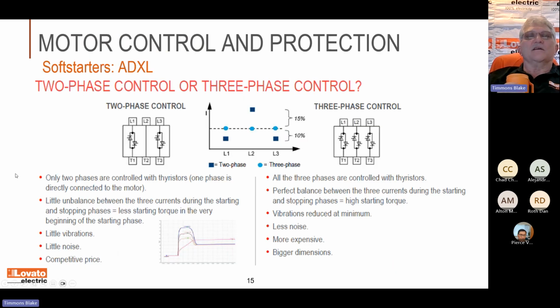So here's a little discussion we get on the different types of soft starters. Sometimes you'll get these soft starters and they'll have 3 SCRs in them, 3 big transistors in them. That's what you're looking at over here on the left. I mean, on the right side, the other left. You'll see you have these SCRs. They're basically triacs, back to back. SCRs are triacs, and you'll use that to ramp up your motor.